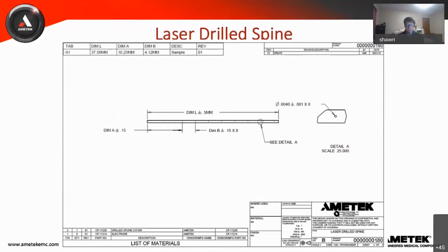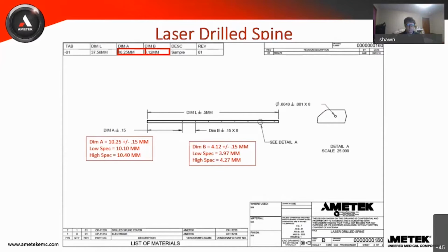Drilled spine. We now go to our laser drilled spine specification. Here you note dim A and dim B. Dim A is where our first electrode is placed. When we drill these tubes, it's where the first hole is placed and all other positions reference off of this hole. So it will be disregarded in the stack up. Dim B, however, is important to where each electrode is placed. The tolerance here is 0.15 millimeters, and we multiply it by 7 because we have 7 electrode locations affected by this dimension. Total stack up here is 1.05 millimeters.